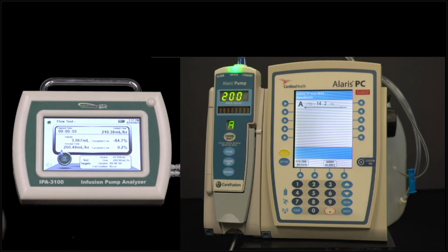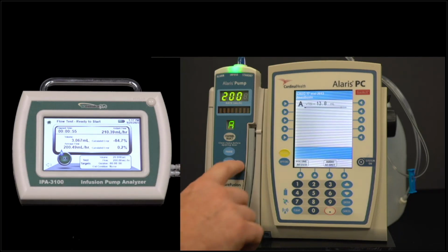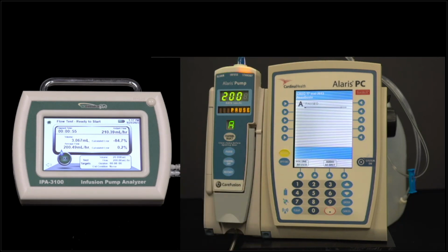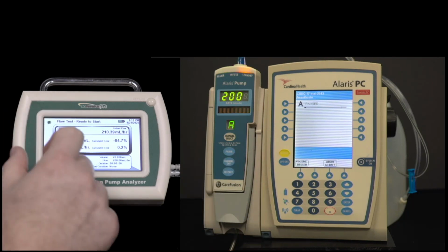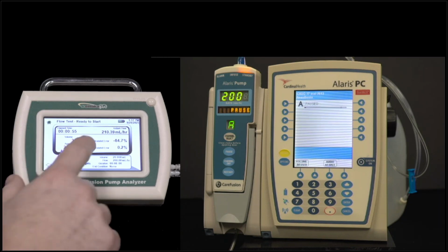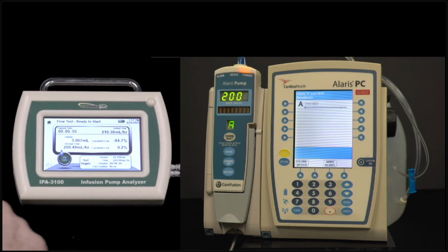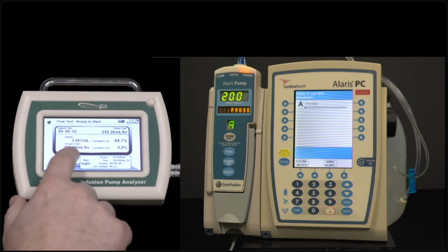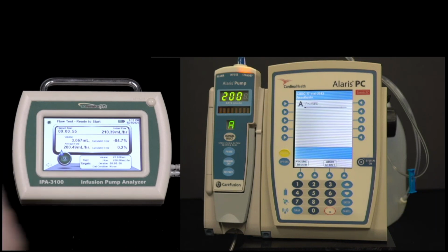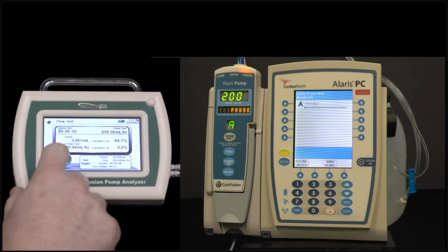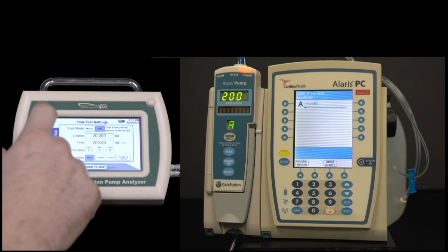In the background, the flow is still running through the IPA-3100. It's just sitting in an idle mode. It's not taking any measurements. So I'm going to go ahead and pause the pump. And at this point, after we ran our test, we can look at the dispensed volume, we can look at the average flow rate, and compare that to our service manual to see if this pump is performing like it should. Okay, so that is flow testing.